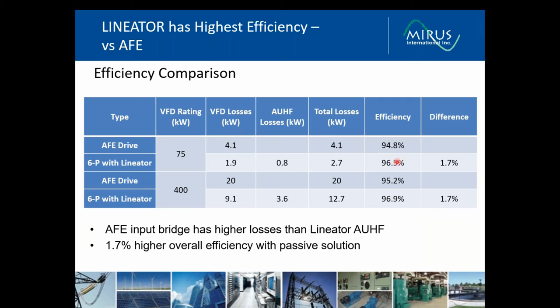Significant improvement in efficiency of the system, with a difference of 1.7% in efficiency, which is really significant. As I said, it's just over half the losses that you would get with an AFE system. Exactly the same relationship or relative performance when we looked at the 400 kilowatt drive.